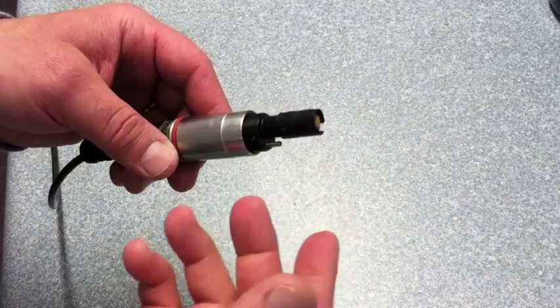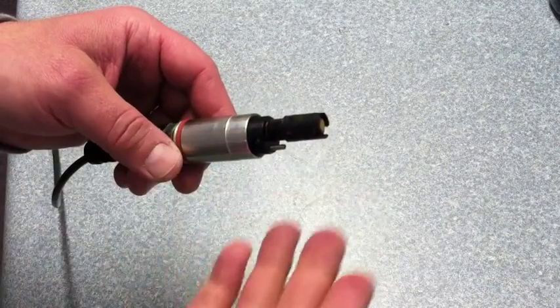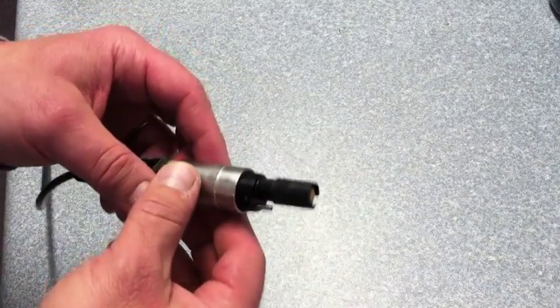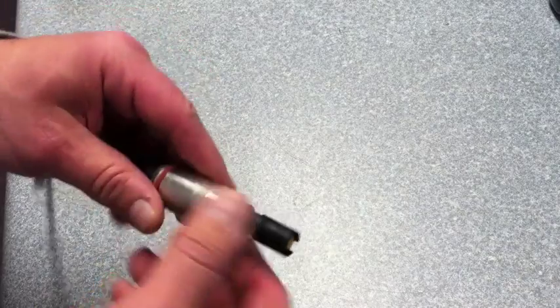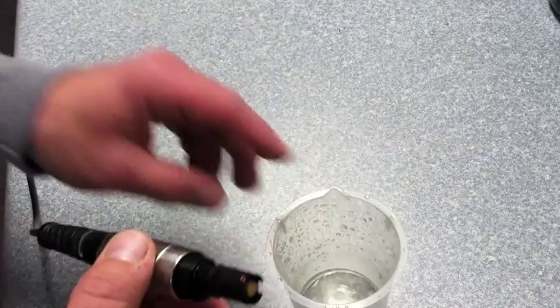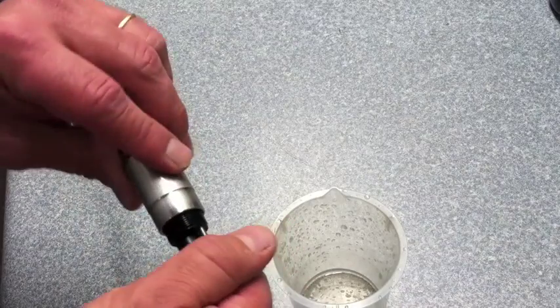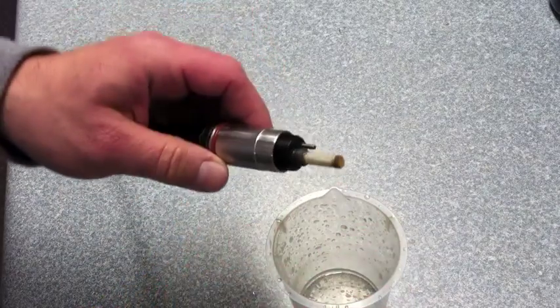Anytime you're not able to calibrate, if it's giving you an error or if the probe is unstable, that might be an opportunity to take a look at the last time that you did a cap change and maintenance on the probe.